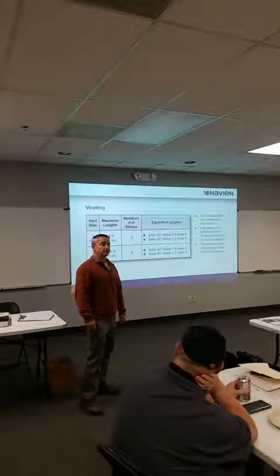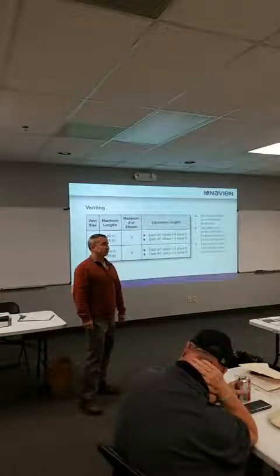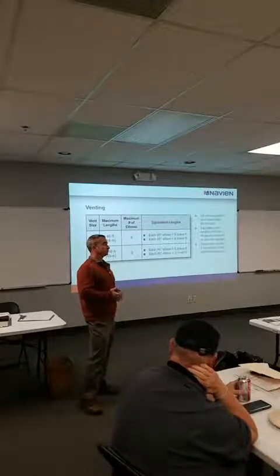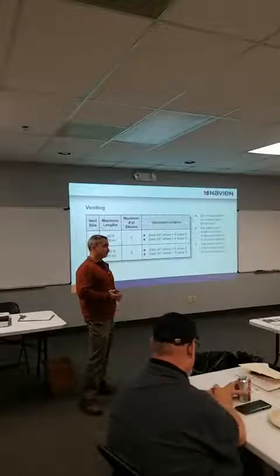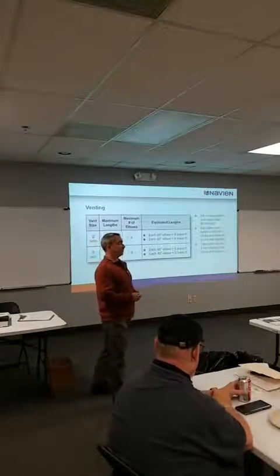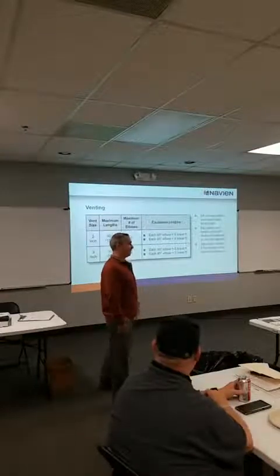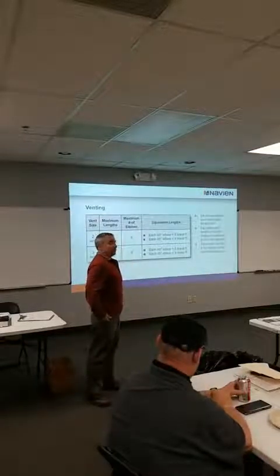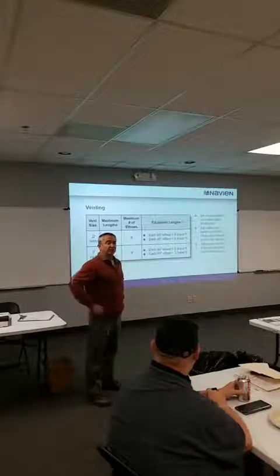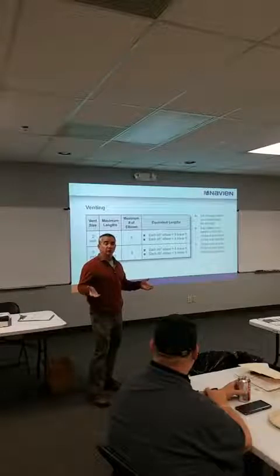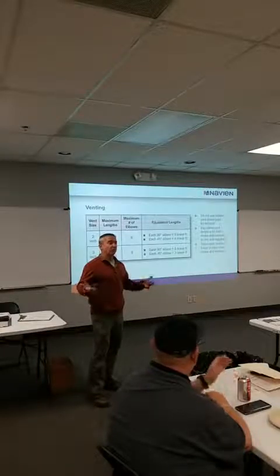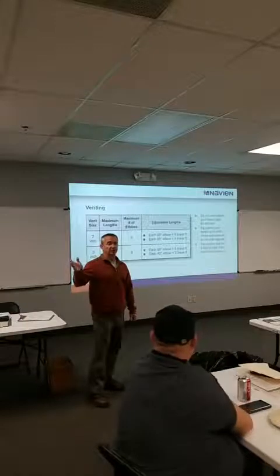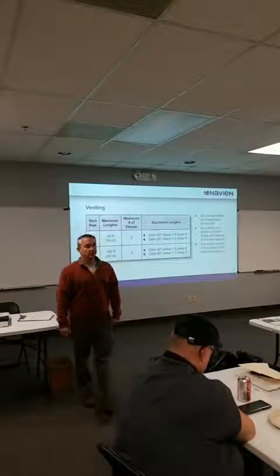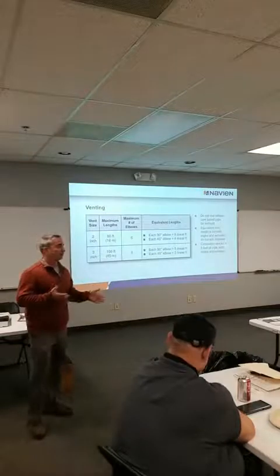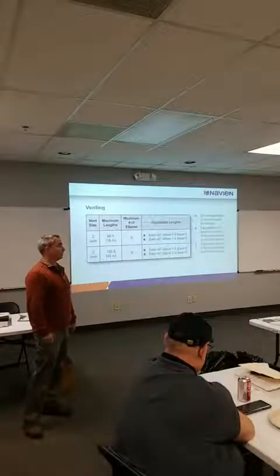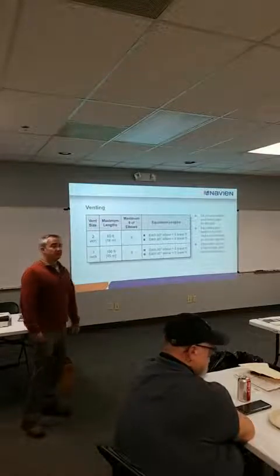Whatever the problem is, the big thing on these products is that if the neutral is broken, you can have 200 volts on one leg and 40 on the other. Yeah, so there's some stuff I check if I think there's an electrical issue, but a lot of times you don't know until somebody tells you, oh yeah, we had a power outage, or we had a lightning strike and we lost this and that. It is sensitive to electricity, to the amps and volts it's getting. We parked an MRI machine on the other side of the wall.